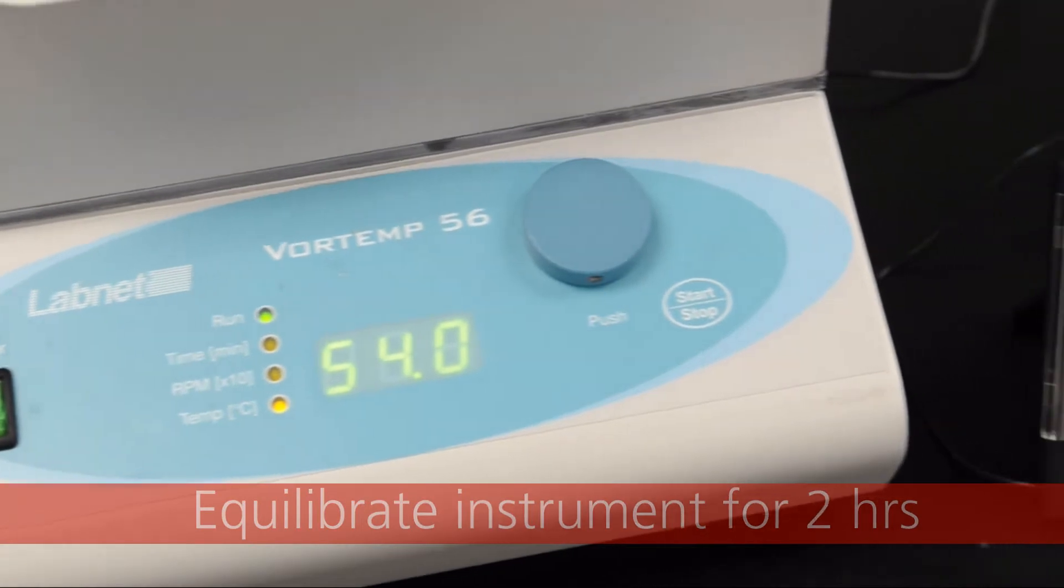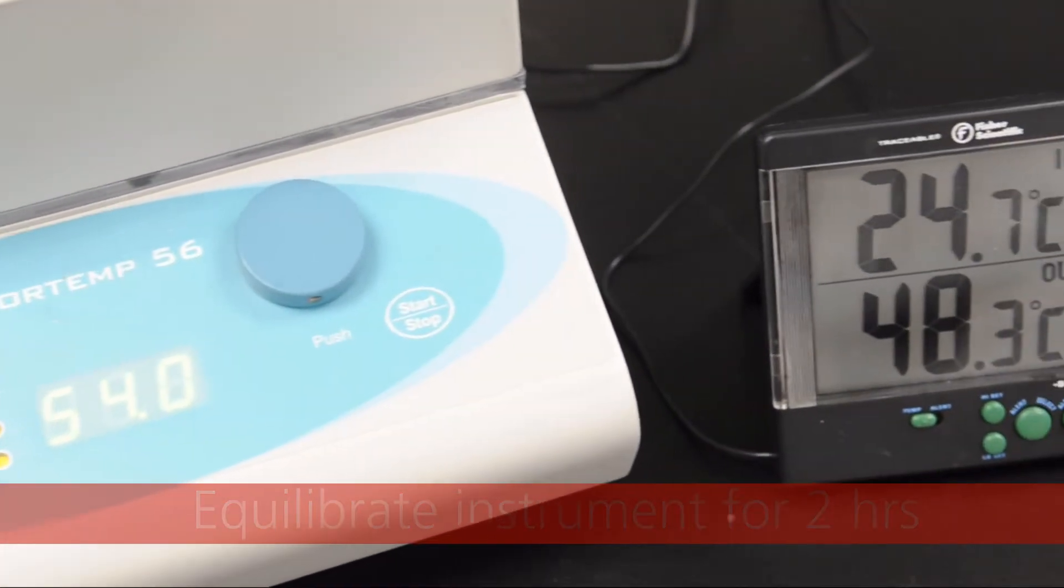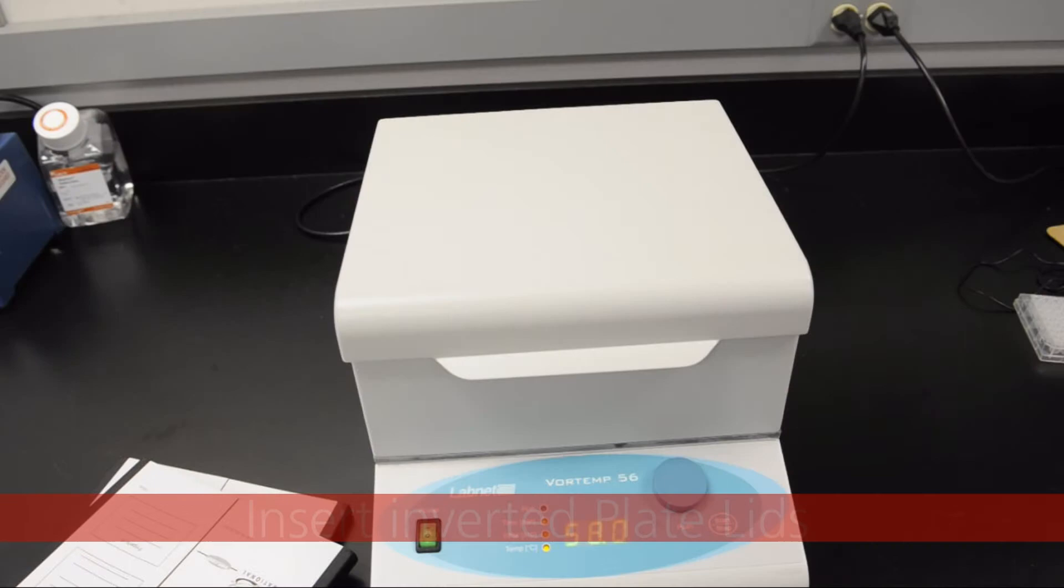press start and allow the temperature of the instrument to reach equilibrium for at least 2 hours.